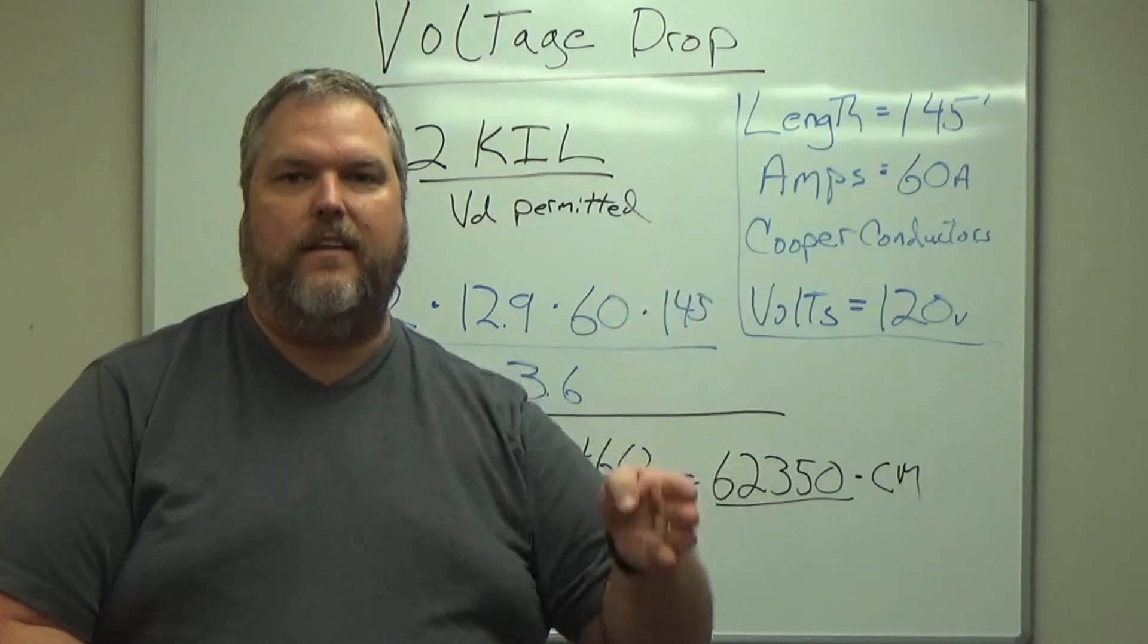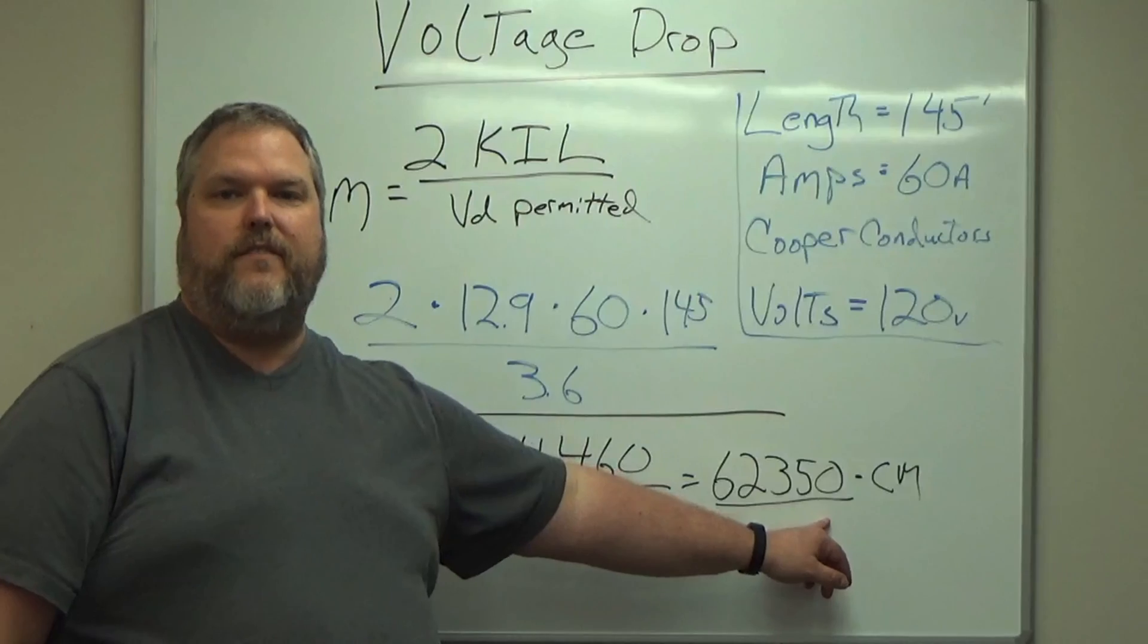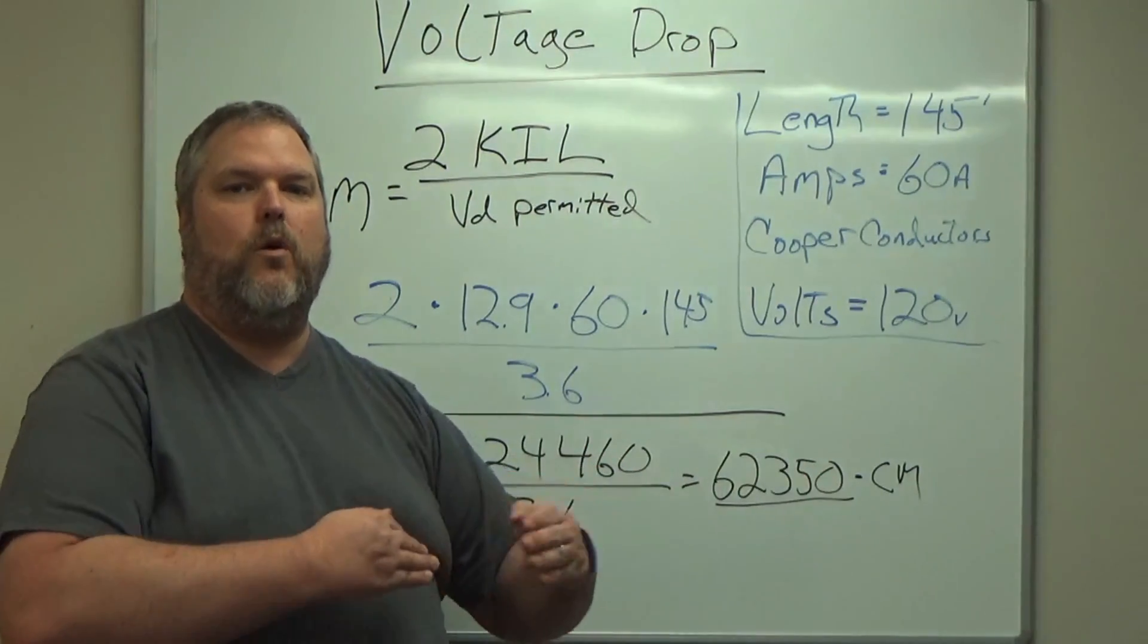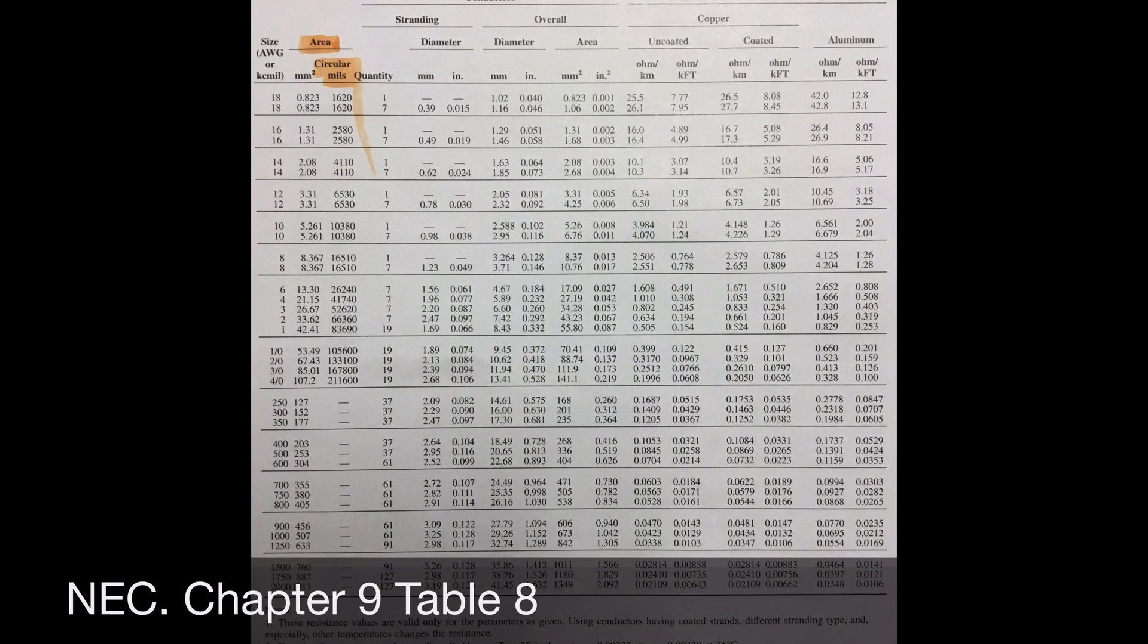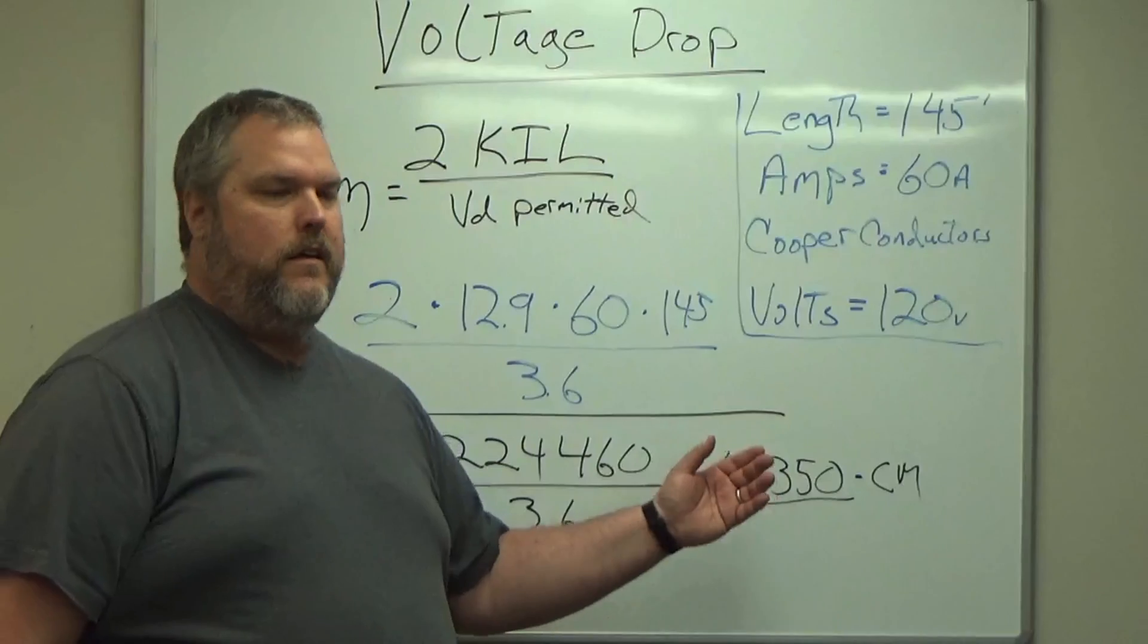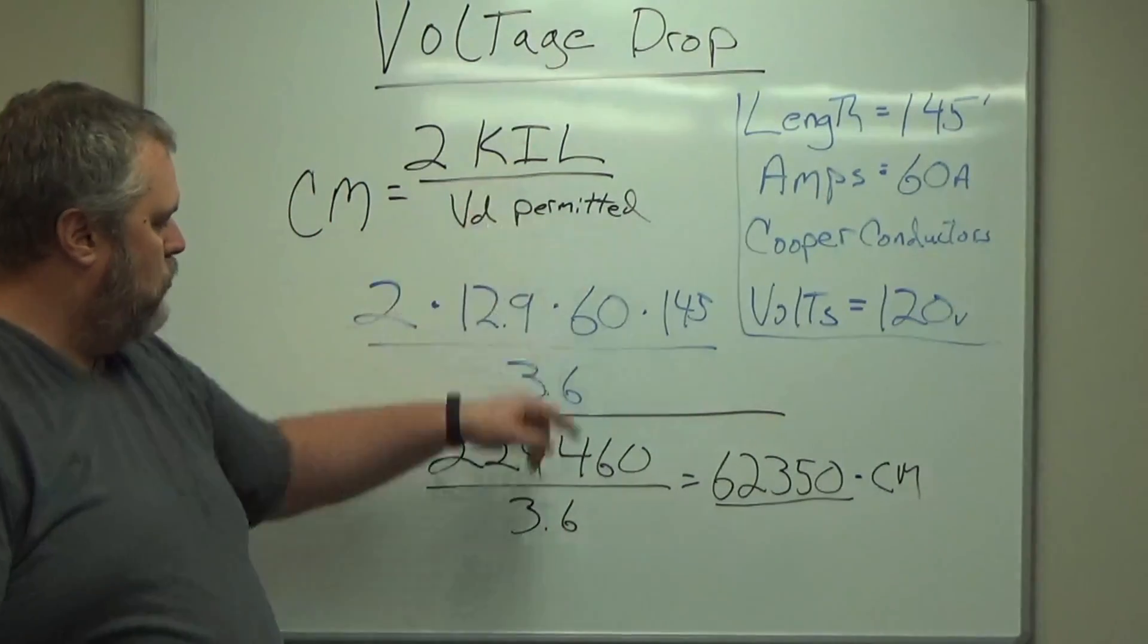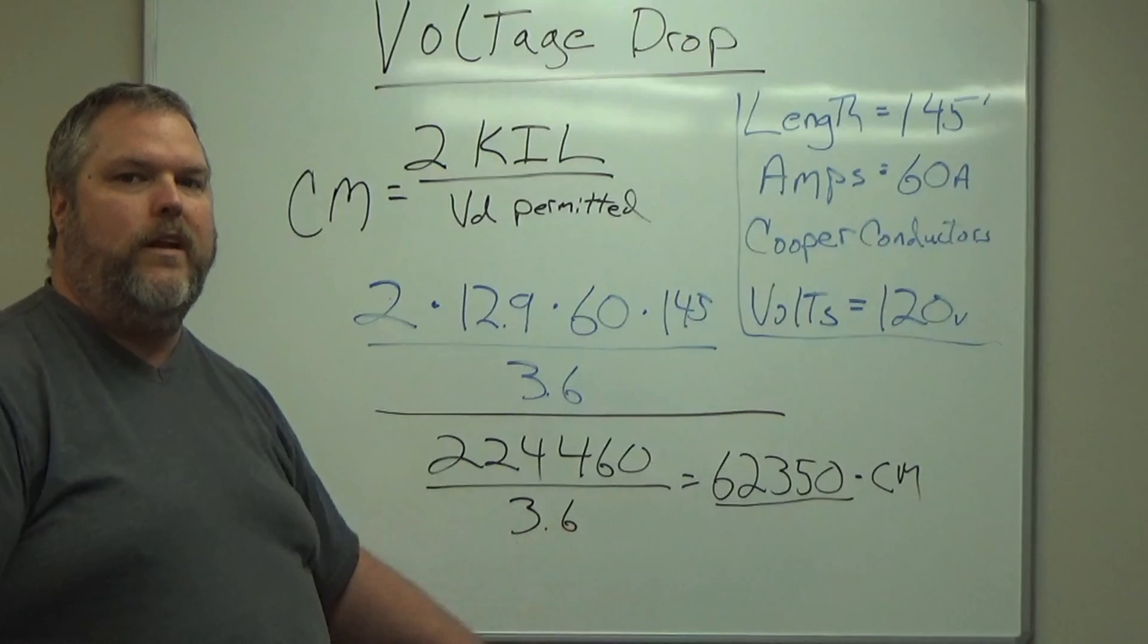Now we just have to refer back to chapter 9, table 8. We're going to find the area. We're going to follow it all the way down until we find 62,350 or somewhere there in between. And as you can see, in order to make this work, to get this voltage drop to be at 3.6, we need to run a number two.